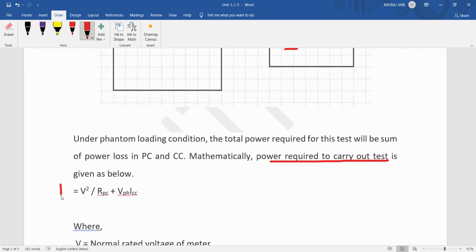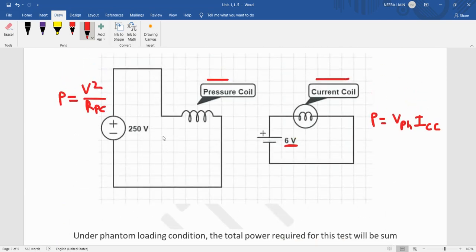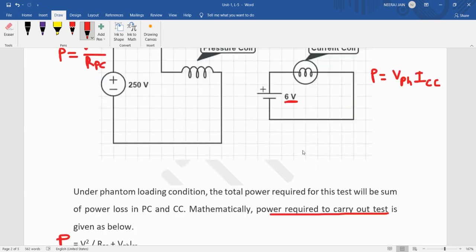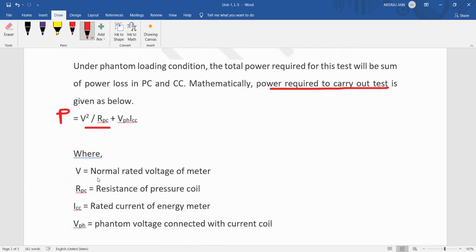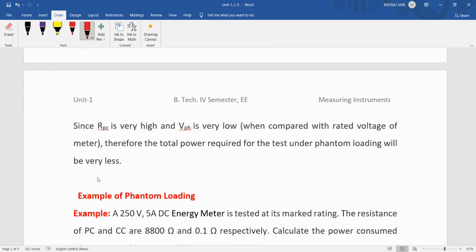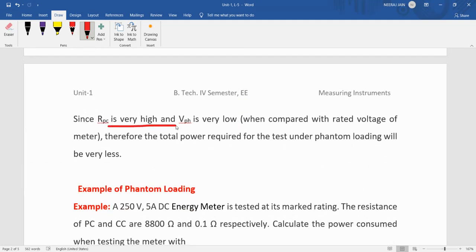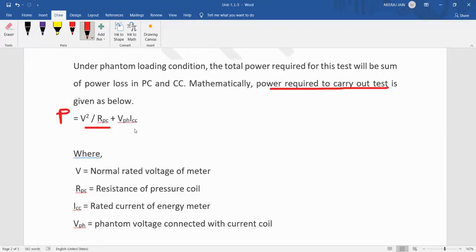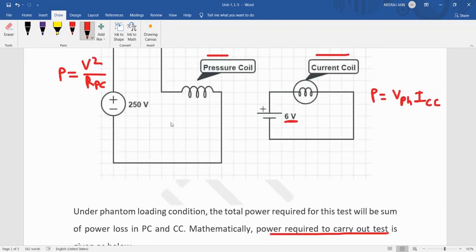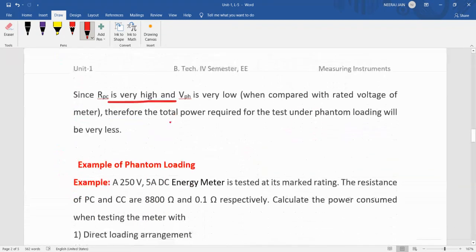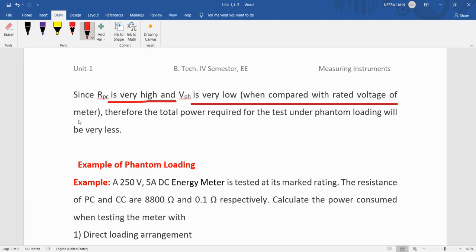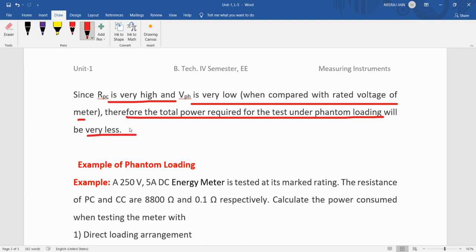The total power P will be the sum of the power consumed by the pressure coil and the power consumed by the current coil. The power consumed by the pressure coil is P = V² / R_PC, where R_PC is the resistance of the pressure coil. Since R_PC is very high compared to the rated voltage of the meter, the total power required for this test under phantom loading will be very less.